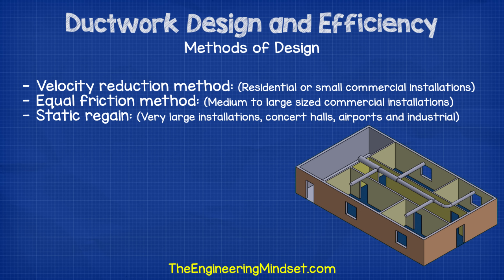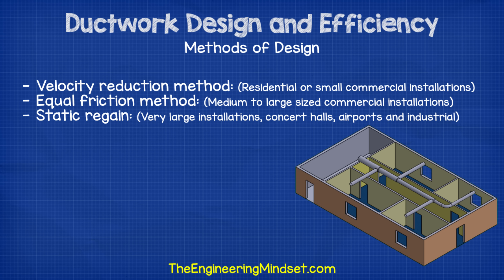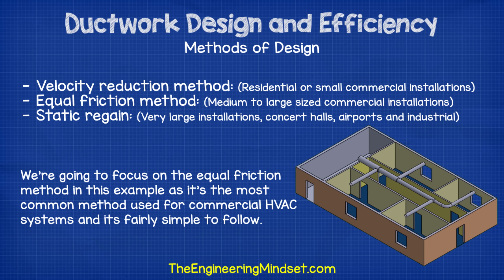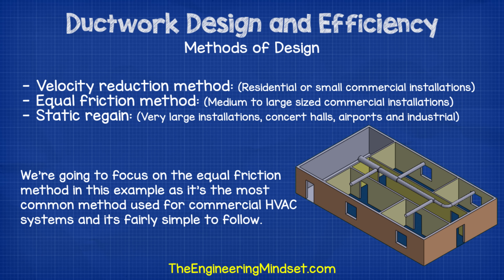Methods of ductwork design. There are many different methods used to design ventilation systems, the most common ways being velocity reduction, equal friction, and static regain. We're going to focus on the equal friction method in this example, as it's the most common method used for commercial HVAC systems, and it's fairly simple to follow. So we'll jump straight into designing a system.